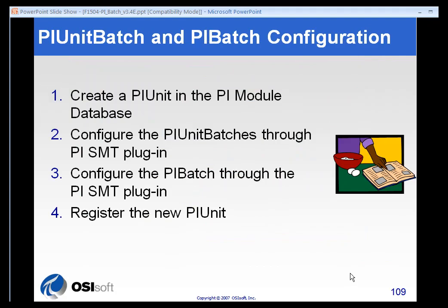All of this is configured with four very basic steps. We first create a PI unit in the module database — that's simply a module with a special parameter set. We then configure our unit batches through our PI SMT plugin. If we have PI batches at a higher level, we configure those using the PI SMT plugin as well. And finally, to get the interface to pick up the batch and start recording, we register the new unit again using the PI SMT.